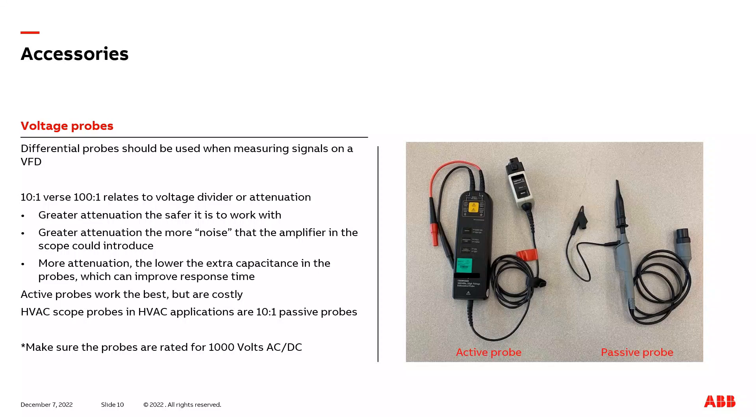One of the big differences you also notice when looking at two styles of voltage probes is active probes are much more expensive compared to passive probes. Whatever type of voltage probe you do select and want to use, make sure it's rated for up to 1,000 volts AC or DC, as you could be measuring signals, for example, on the DC bus that are 850 volts or even higher. So you want to make sure the voltage probe is safe to work with at these high voltages.